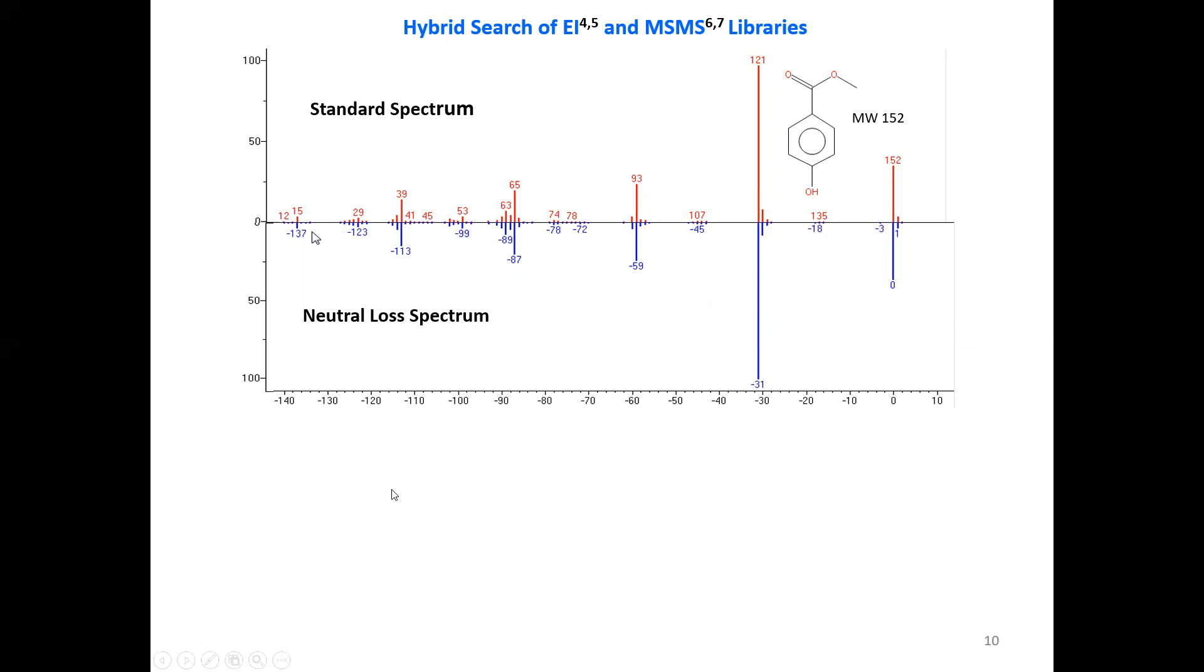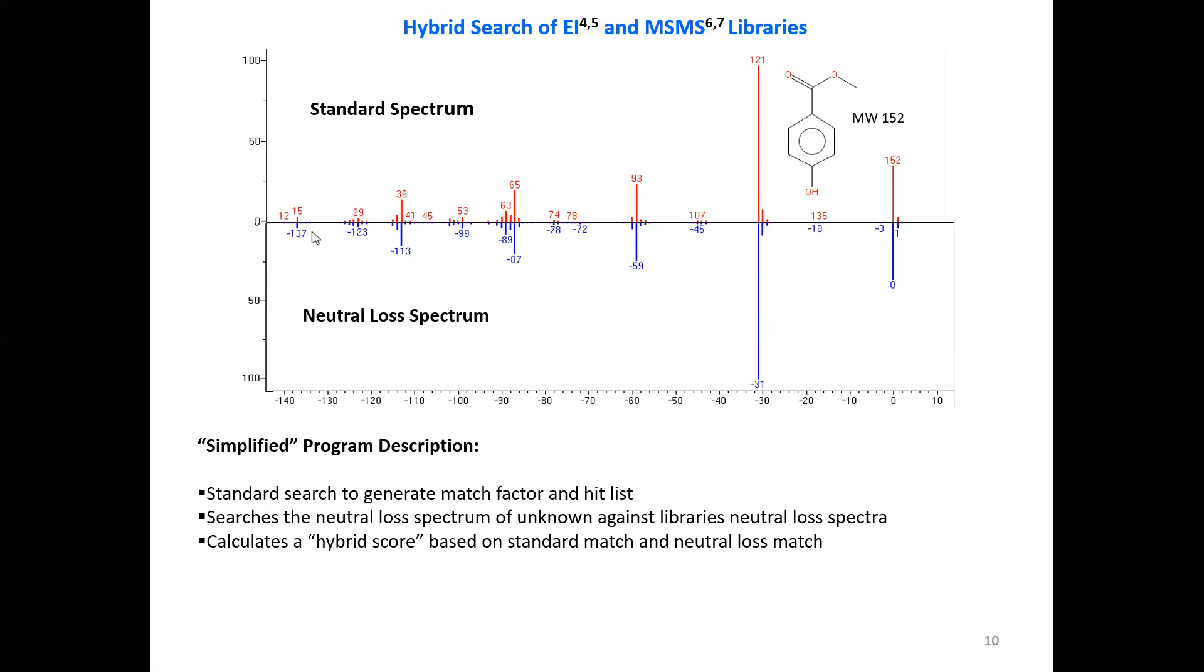So what does it do with this? This is somewhat simplified, but the standard search is used to generate the standard match factor and hit list. Then it searches the neutral loss spectrum of the unknown against the library's neutral loss spectra. It calculates a hybrid score. It takes the original score from the standard search and calculates the neutral loss search and then creates a hybrid score that's weighted properly to get a final factor or search or hit. Also each compound in the list has a delta mass associated with it, which is the difference in the molecular weight of the unknown and the library hit.